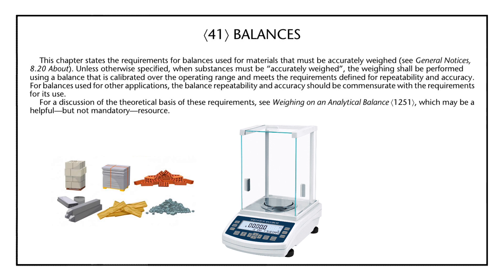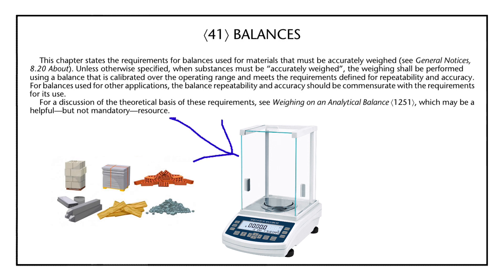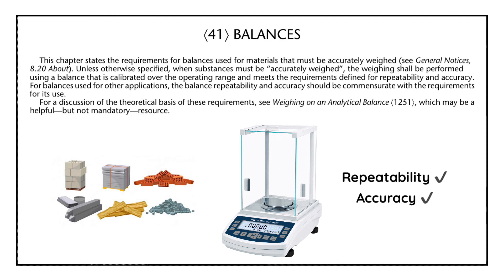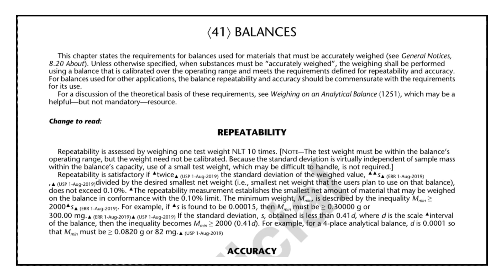Let us understand this statement with the help of an example. Suppose we have to weigh any material accurately using this balance — before using this balance, I have to make sure that this balance is meeting the requirements of repeatability and accuracy as mentioned in USP Journal Chapter number 41. In USP Journal Chapter number 41, there are two balance calibration parameters: repeatability and accuracy.